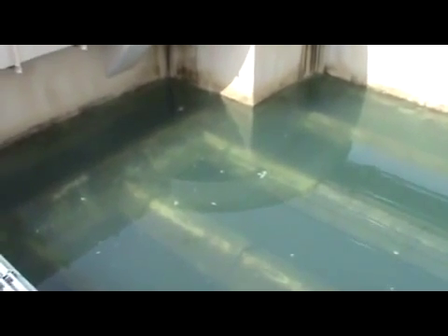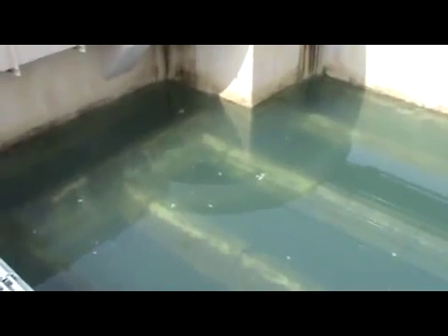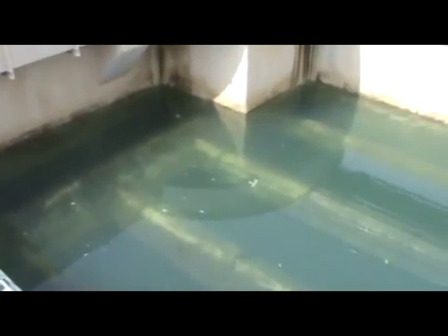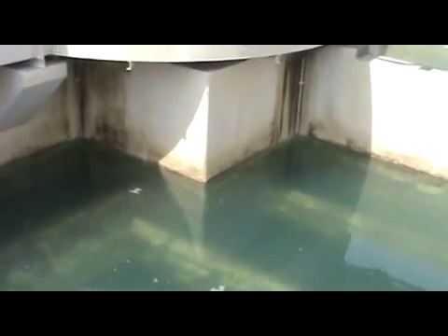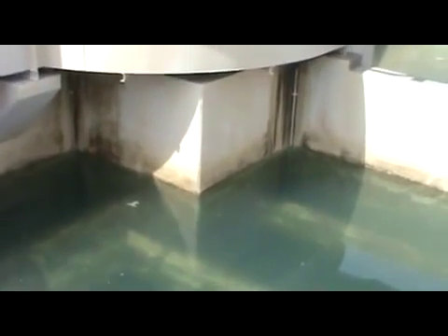An important thing to do while you're draining and during the backwash process is to make sure you surface wash. You see right here that there's a hose out on the ground, and that's what that hose is for: washing the surface, washing the sides of the bin. If you do not wash the surface properly through the process, you can have the creation of what's called mud balls, which can cause breakthrough and other material down the road in the filters.